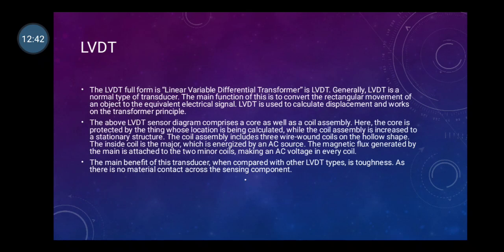When core is at null position, voltage induced in two parts of the secondary are equal and opposite. Therefore, output voltage is equal to V1 minus V2, mostly 0. But when core is moved to left or right movement from its null position, that means V1 is not equal to V2. At null position, V1 is equal to V2, but at its move towards from a null position to upward side or a downward side, then V1 is not equal to V2. Therefore, output voltage is equal to V1 minus V2 and having some value. This voltage signal convert into a pressure by a calibration and indicates a pressure on the calibration scale. So this acts as a secondary transducer.